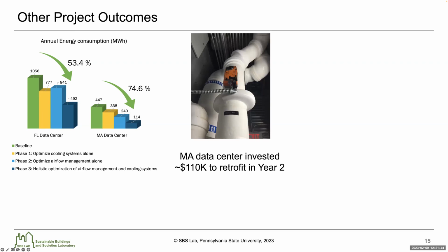Here is a chilled water regulation valve to control the amount of chilled water used to cool the air. We found that the data center's cooling system is designed for 100% capacity of the computer room, but in the real world they only use about 50% of total capacity. As a result, they overcooled the supply air to the computer room and had to use an electric heater to reheat the air back to the desired temperature, which is a huge waste. By adding this chilled water regulation valve, they can avoid the overcooling problem and don't need to reheat the air.